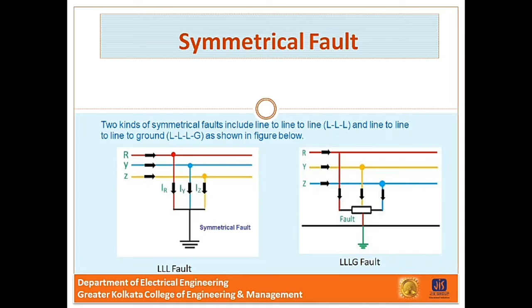Now a rough occurrence of symmetrical fault is in the range of 2 to 5% of total system faults. However, if these faults occur, they cause very severe damage to the equipment even though the system remains in a balanced condition. The analysis of this fault is required for selecting the rupturing capacity of the circuit breaker, choosing the relay settings and other protective switchgear. These faults are analyzed on a per phase basis using the bus impedance matrix or Thevenin's theorem.